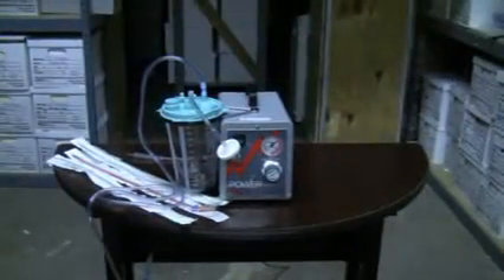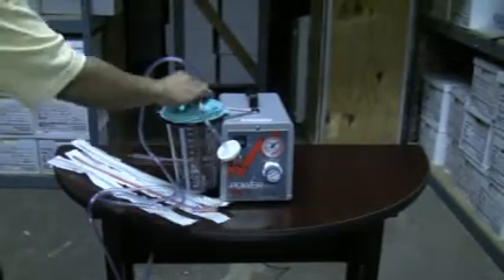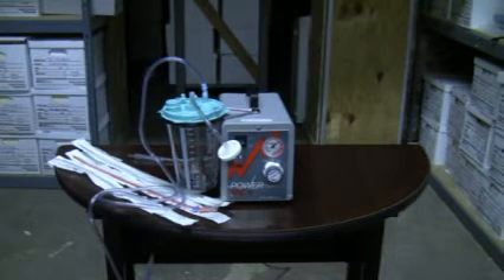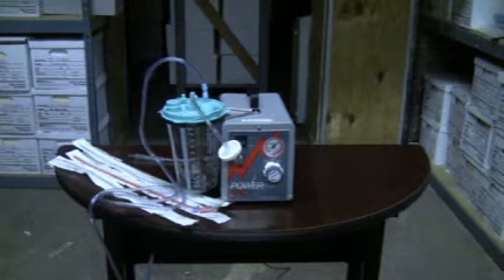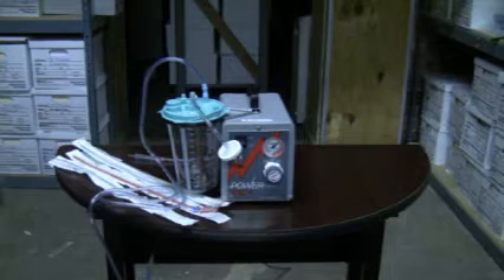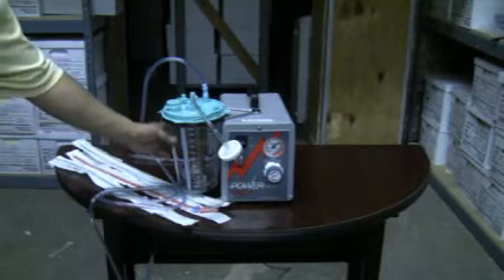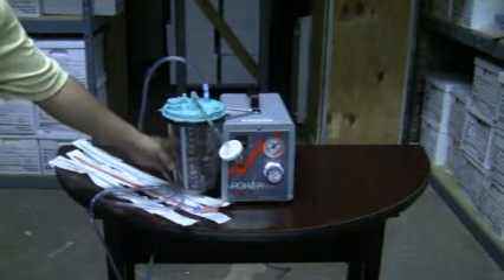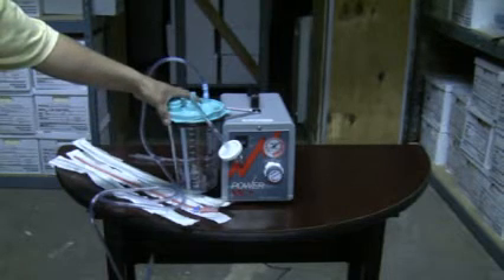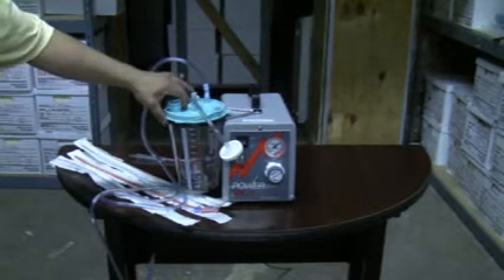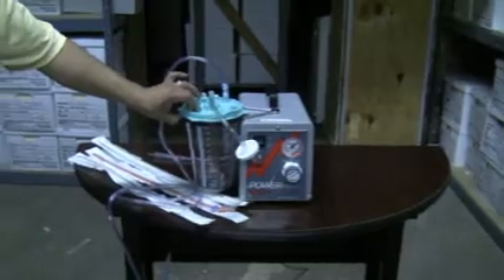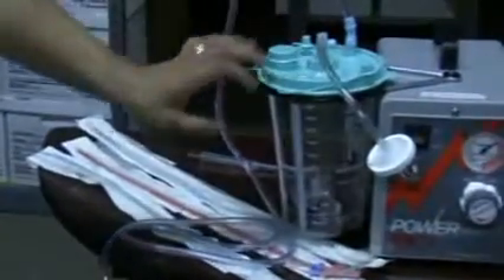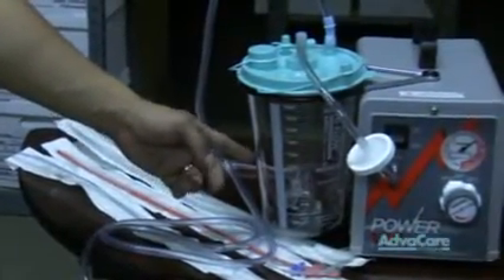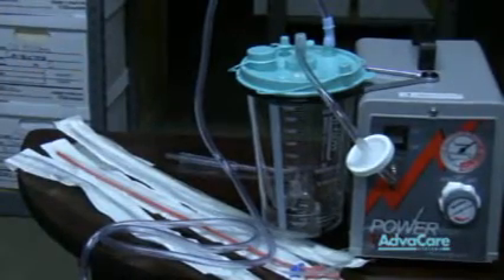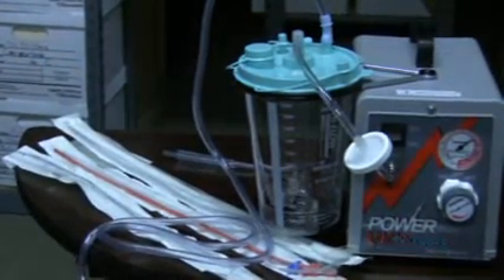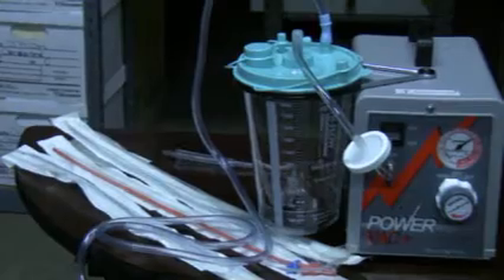If you did check your connection here and here, and you still do not have any suction pressure present, you do want to inspect your suction canister for any cracks or for the lid not to be completely sealed. If it is not sealed correctly, please tighten and secure the lid. If there are any cracks in the lid and your canister is faulty, please contact AdvaCare Systems to have your canister switched out with a new one.